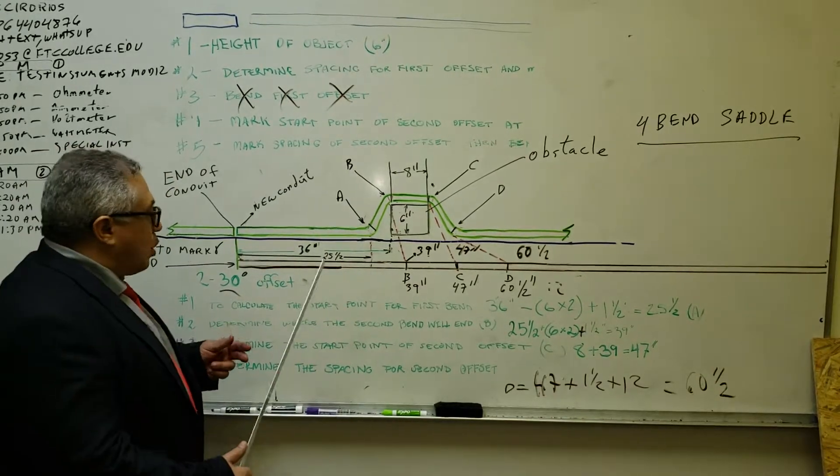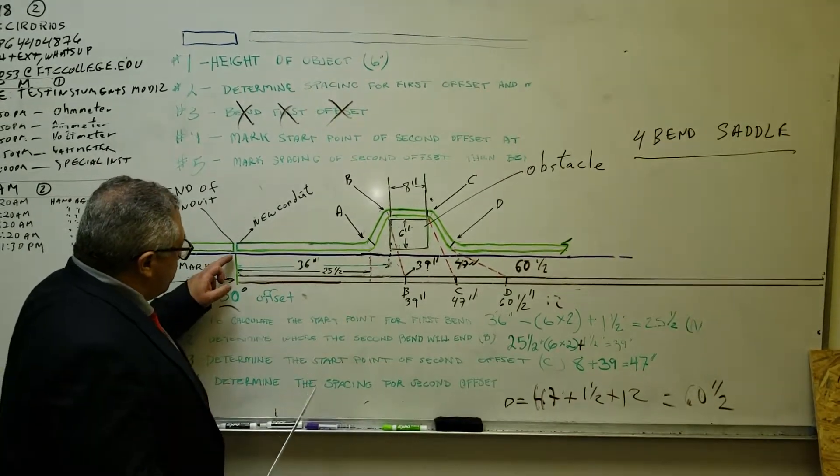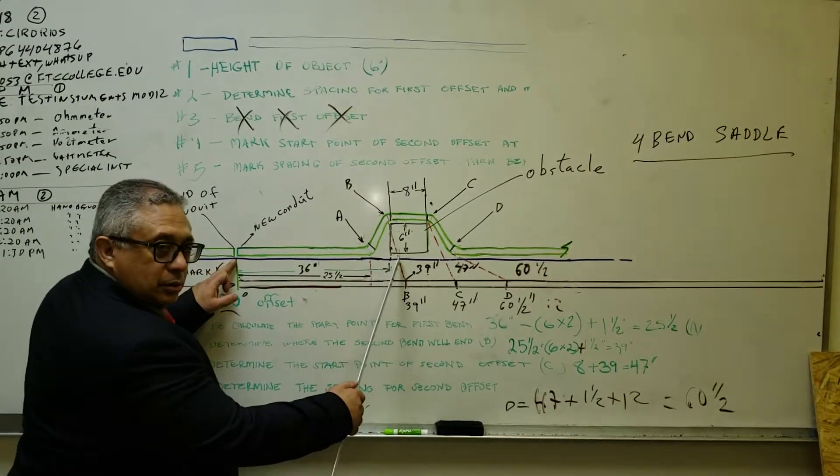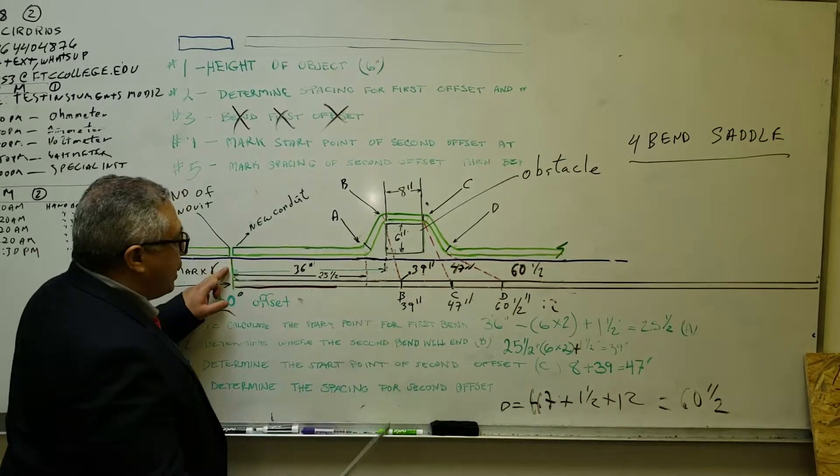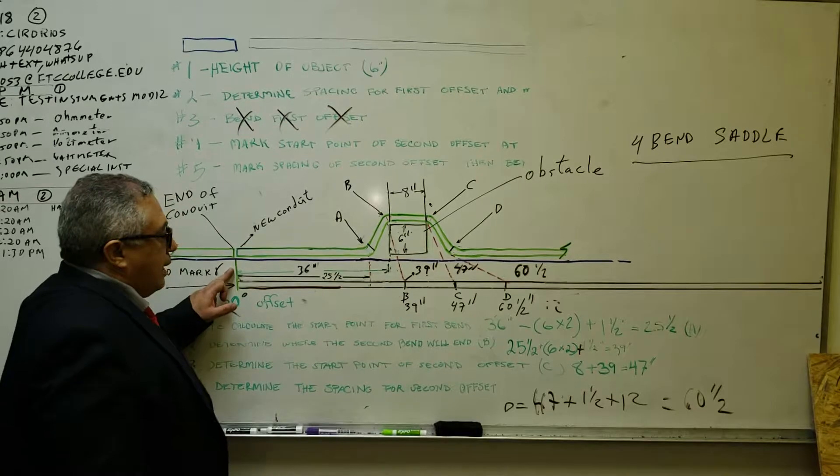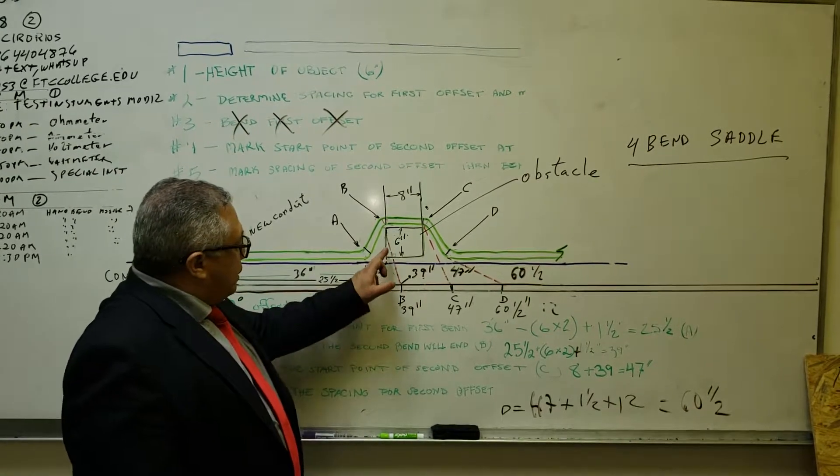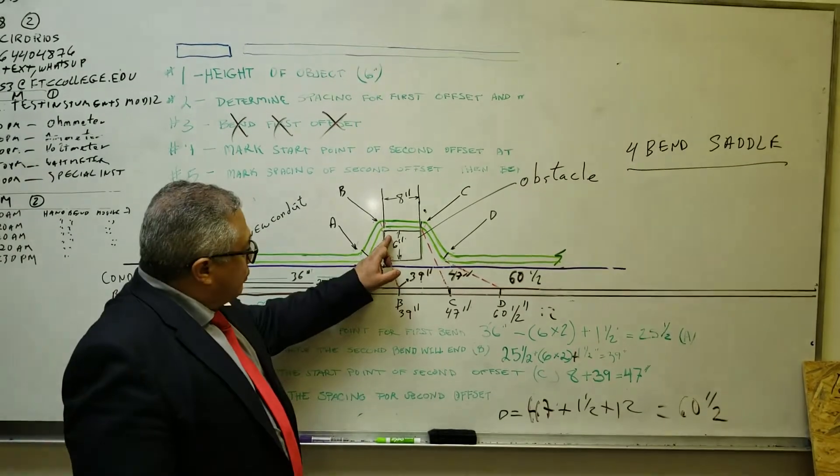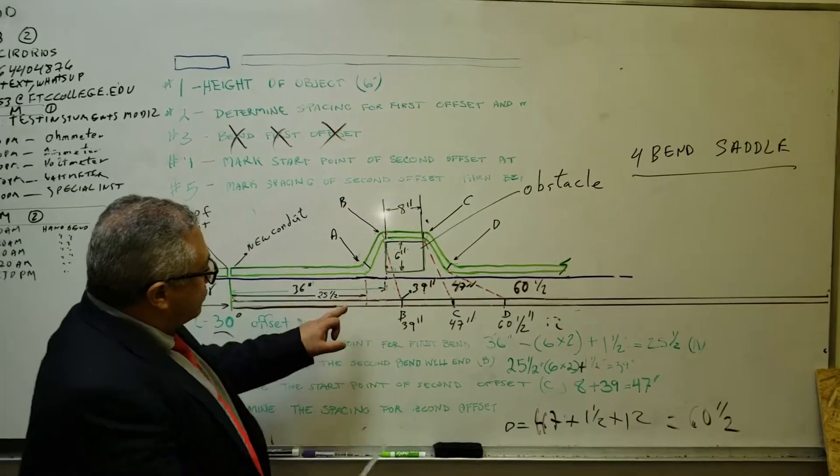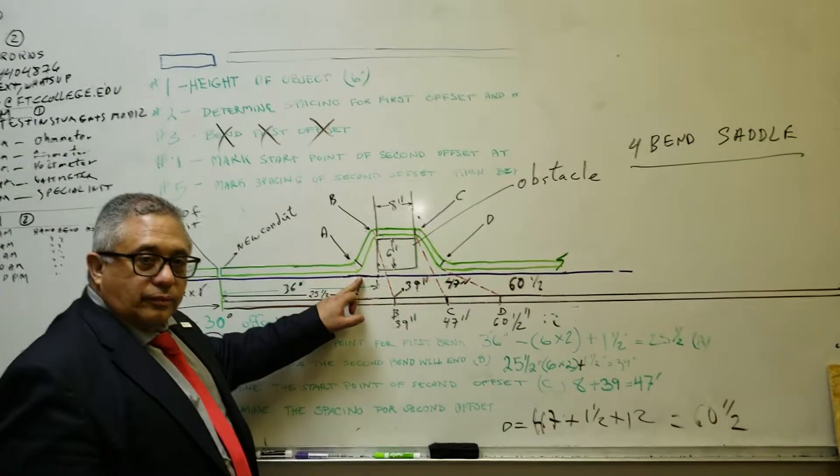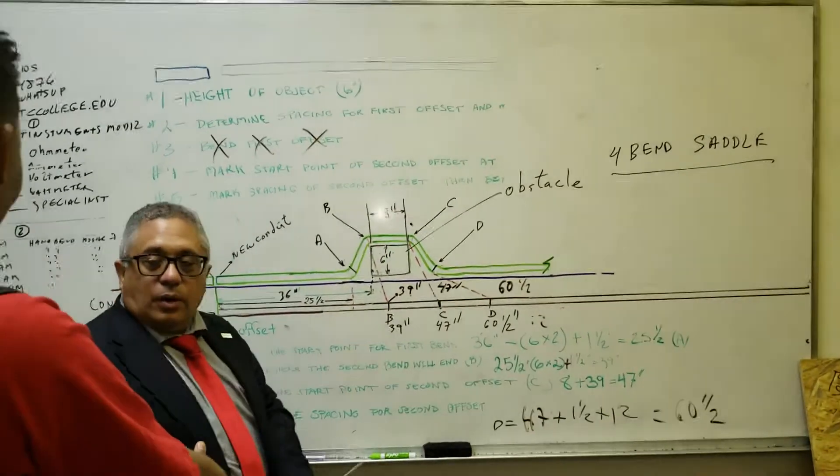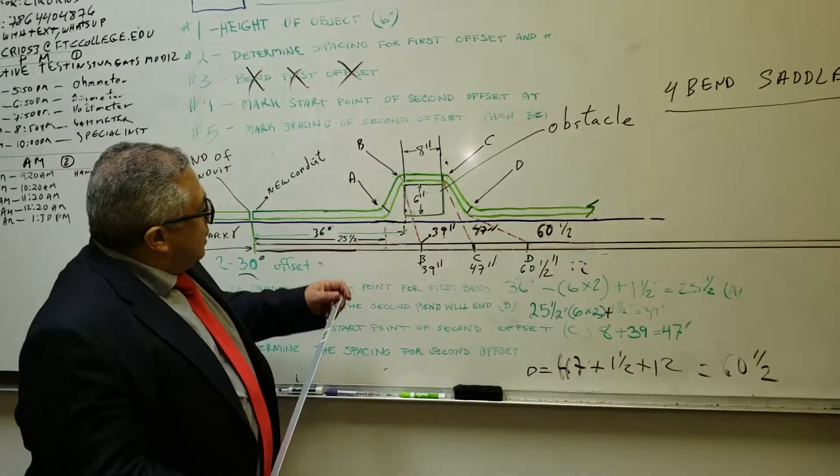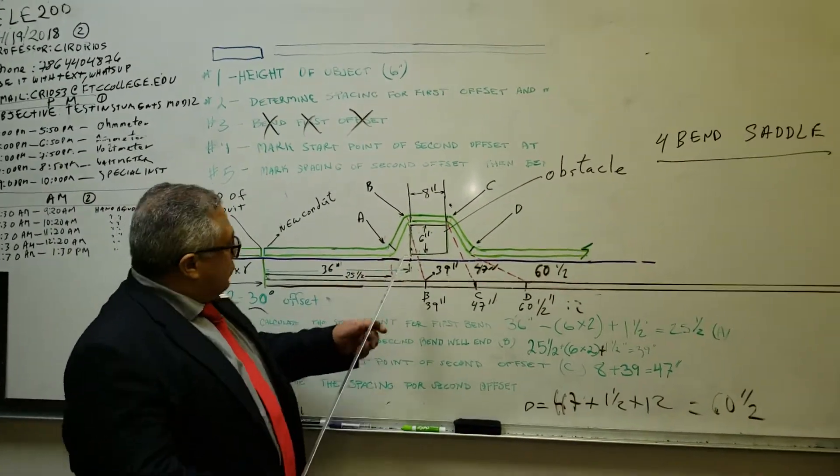So in order to overcome this, the first thing that you need to do is measure the distance between the end of your conduit and the obstacle. In this case, it's 36 inches. Now with this measurement, we need to apply the rule of the table to find out what is the distance. We know that this distance is, for 30 degrees, the height times the multiplier, which is 2.